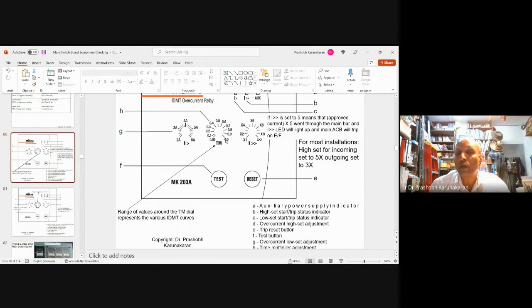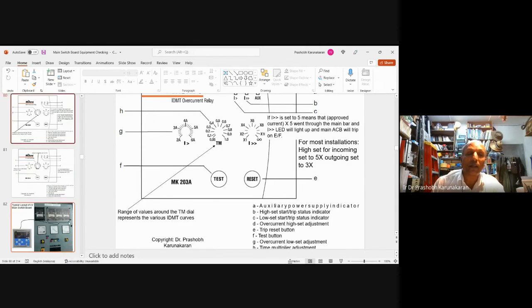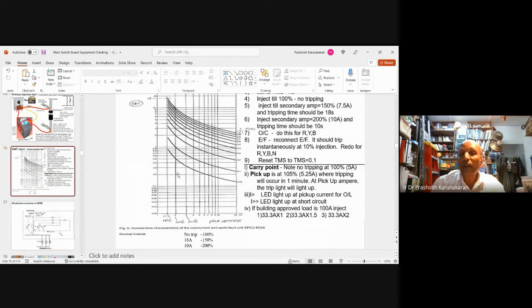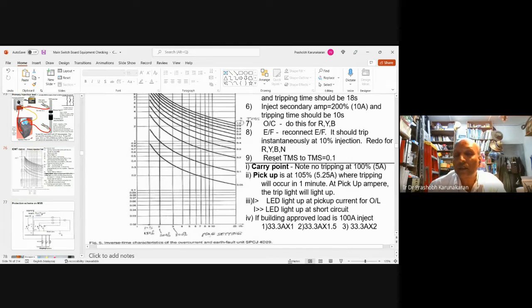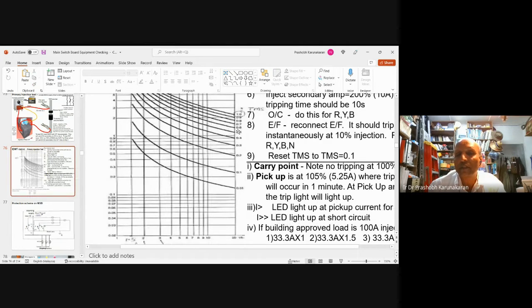And after you finish the test, you must tune back to 0.5. You must always tune back to 0.5. Only for testing, you tune to 1. That's why we use the 1 here. You see? This graph got so many graphs. This is 1. When you tune to 1, you use this graph. In normal case, it is 0.5. In normal case, it's this graph, 0.5. Only for testing, you tune to this one.